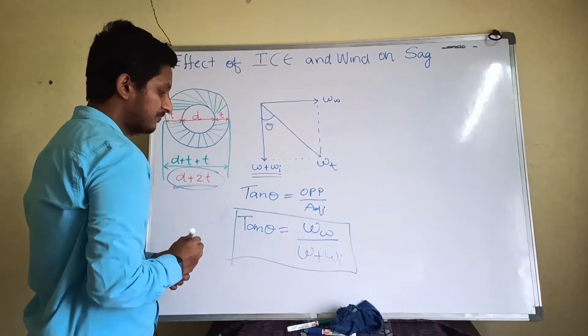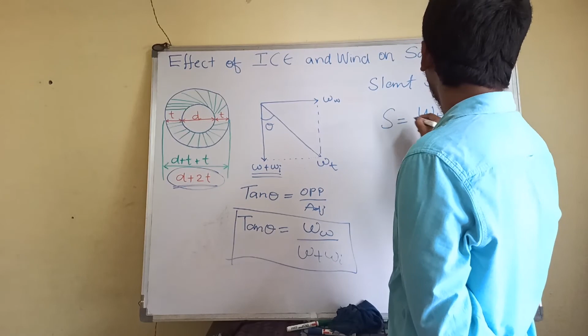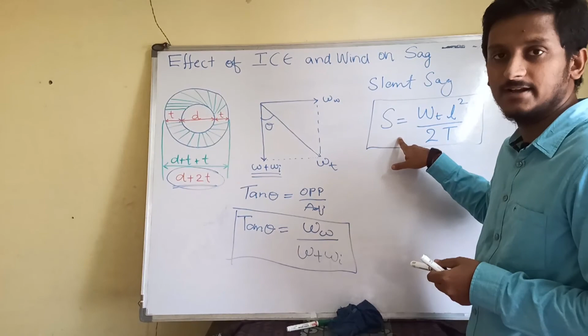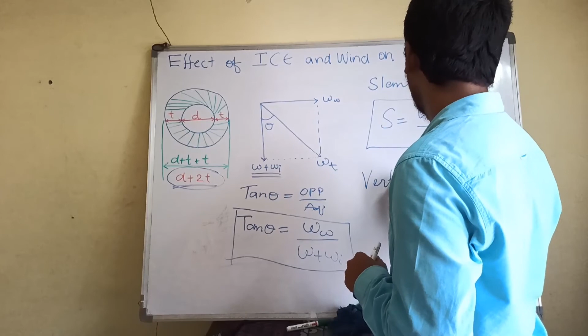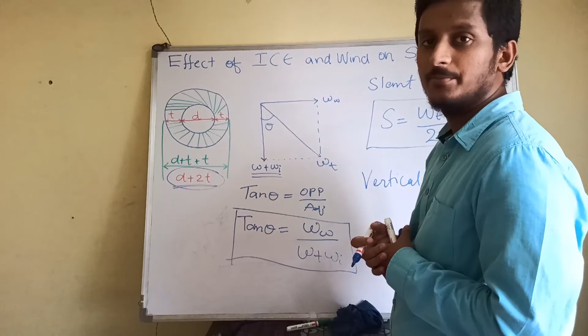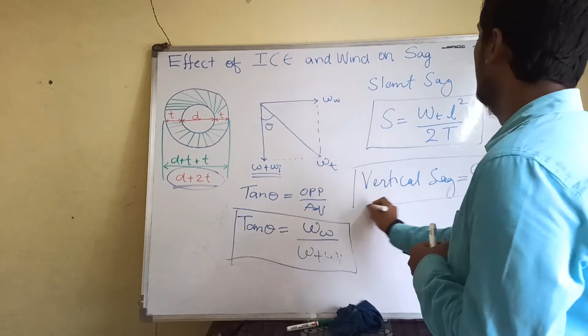Now I am going to tell you the formula for the slant sag. That is S is equal to WT into L square by 2T. This formula you can see in the lecture of sag calculations. I have given you there that y is equal to Wx into x square by 2T. So from there this derivation is there. But at this point we are going to see this is the slant sag. And now you want to see the vertical sag formula. You see in the diagram, that is the vertical component. So vertical sag is equal to S cos theta. This is the vertical sag formula.